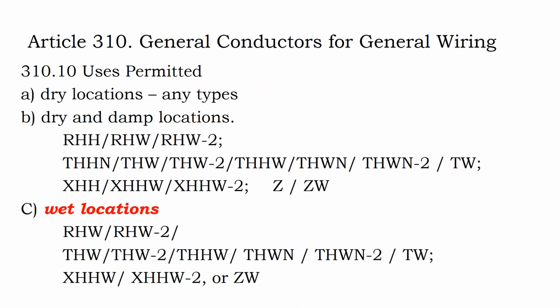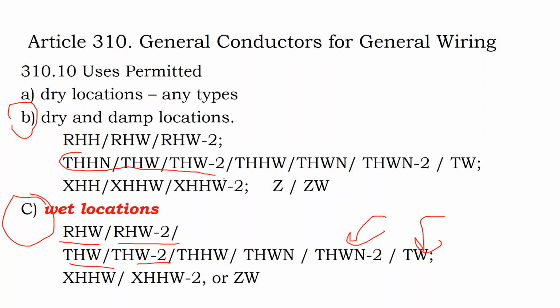So now we start getting into conductor sizing differences, and there's a wide variety of conductor labels, but there are some patterns that emerge. Here we have conductors for dry and damp locations versus conductors for wet locations. What we see is wet locations is RHW, RHW2, THW, THW2. Wet locations have this W on them. What gets confusing is you see THHN, THW, THW2. This is like a cross-listed cable for both wet and dry locations.